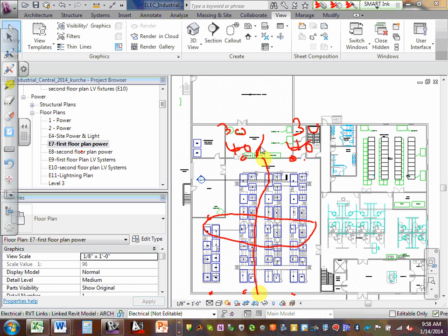It's just like the speakers. Gotcha. 10 feet in from that wall, 10 feet in from that wall, you place your first device, then you can go 20 feet, 20 feet. But everything is always measured from the device being the center of the box, and then you can go either direction as far as its coverage. Okay, so you've got your smoke detection in the manufacturing area now.